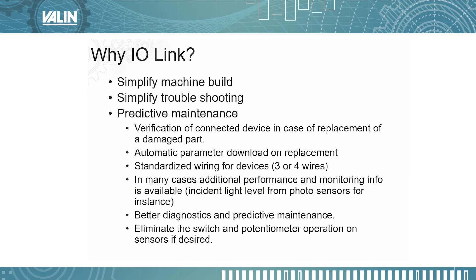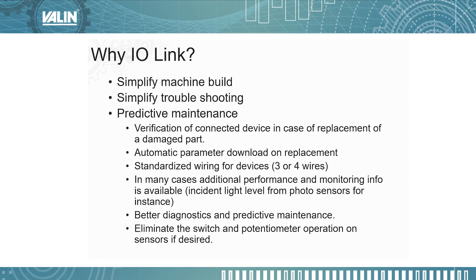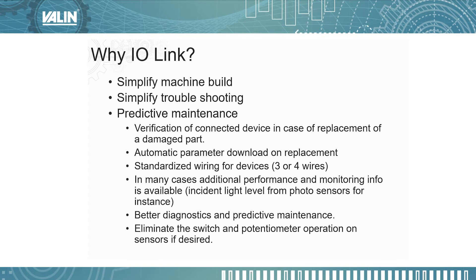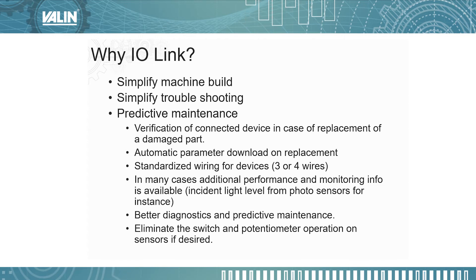So why do you want to use IO-Link? For one, it can simplify the machine build. When building machines, you might have sensors or products from different vendors with their own specific wiring diagrams. If you're using IO-Link, all IO-Link-enabled devices connect in the same fashion. You have either three or four wires, and there are three or four connection points on the IO-Link unit — so every three-wire IO-Link device connects the same way, and every four-wire device connects the same way.